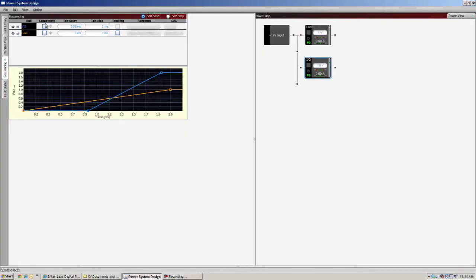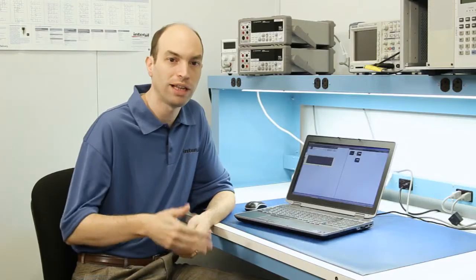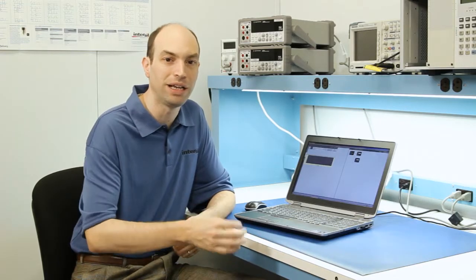The next box is the sequencing box. Now automatically you are sequencing everything from a time-based standpoint. But one of the benefits of the digital power devices is a DDC bus that links every single one of the products. This allows you to have event-based sequencing.